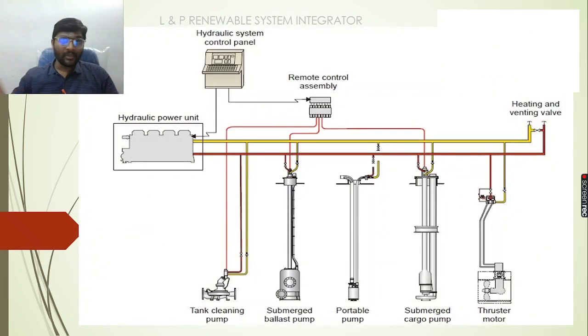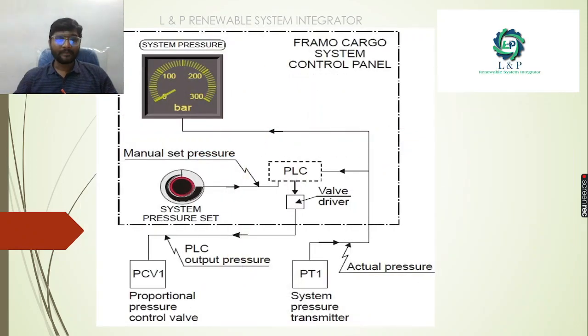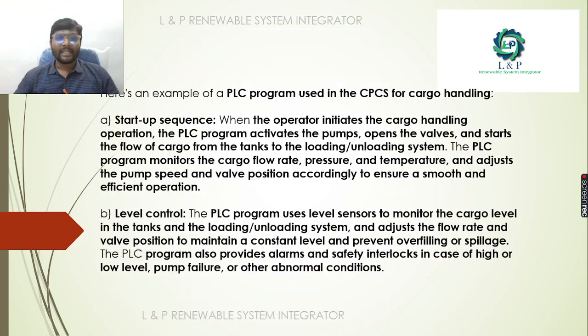Okay, so this is how it looks. It's the overall view. Next, this is another view of how the cargo system control panel looks. We have the manual set pressure points. We have the PLCs which drive the valves, and also, using the proportional integral derivative PID loop, it controls the valve. It takes the input from the pressure transmitter and it controls the valves. Next, how does this cargo control system work?